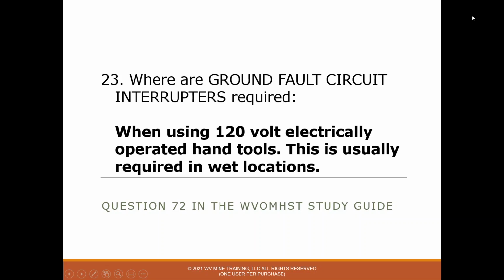23, where are ground fault circuit interrupters required? And the answer is when using 120 volt electrically operated hand tools, and this is usually required in wet locations. So, wet locations at prep plants, surface areas of underground mines, concrete slabs in contact with the earth. There are lots of definitions of where this is required, but the 120 volt electrically operated hand tools in wet locations. And you have ground fault circuit interrupters at your house, in your bathrooms, in your kitchen, maybe outside. Again, 120 volt electrical circuits have GFCI.